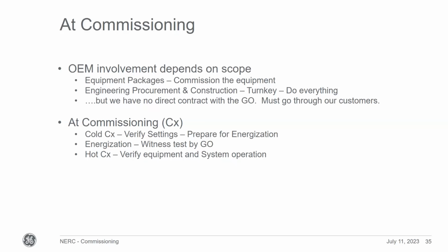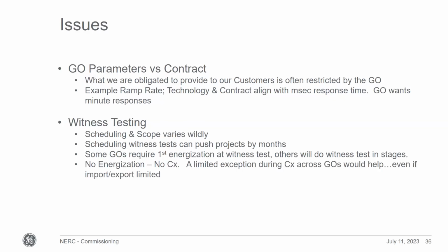So I went through what happens at commissioning: cold commissioning, where we verify the settings and prepare for energization, basically energize, which is the witness test, and then hot commissioning, where we verify equipment and system operation. I'm just trying to keep it simple here. And then the next slide, Alex: what issues do we really see with all this? The process is simple, but there's the grid operator parameters versus the contract.